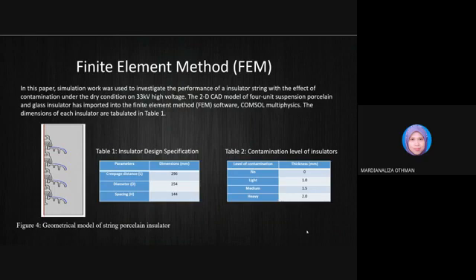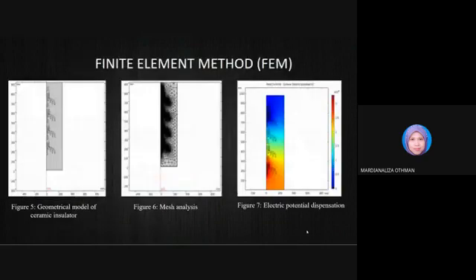Table 2 is for the level of contamination of the insulators: no contamination is 0 millimeter, light is 1 millimeter, medium is 1.5 millimeter, and heavy is 2 millimeter. Okay, this is for methodology.